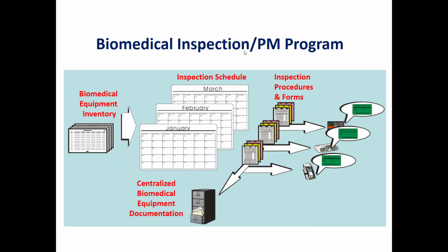Another policy and procedure in clinical engineering, which helps to organize the work in the clinical engineering department, is related to preventive maintenance management. First of all, we have the biomedical equipment inventory, based on which we will make a schedule which covers a whole year. In each month, we will make IPMs for certain devices, and we assign these IPMs to biomedical technicians and clinical engineers.